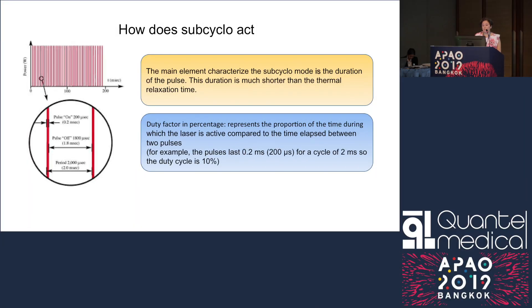The main element characterizing the SubCyclo mode is the duration of the pulse, which is much shorter than the thermal relaxation time. The duty factor, expressed as a percentage, represents the proportion of time during which the laser is active compared to the time elapsed between two pulses. For example, if the pulse lasts 0.2 milliseconds (200 microseconds) for a cycle of 2 milliseconds, the duty cycle is 10%.